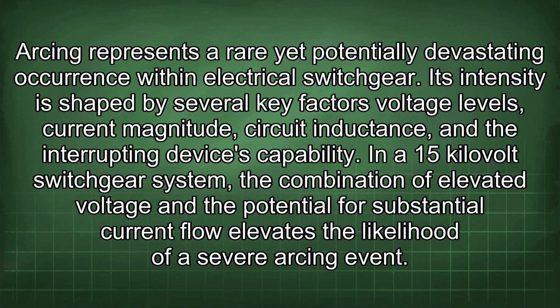Arcing represents a rare yet potentially devastating occurrence within electrical switchgear. Its intensity is shaped by several key factors: voltage levels, current magnitude, circuit inductance, and the interrupting device's capability. In a 15 kilovolt switchgear system, the combination of elevated voltage and the potential for substantial current flow elevates the likelihood of a severe arcing event.